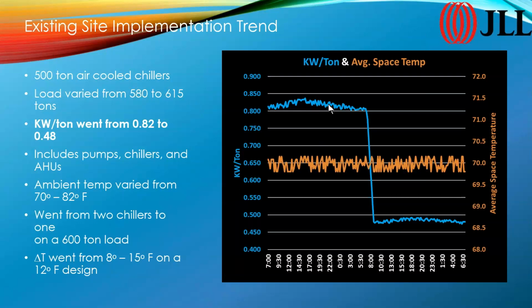We were running with 2 chillers up top, and when we finished the process, we had a 600-ton load, and we were running with 1 chiller quite easily. It was running around 75%, something like that. So a 500-ton chiller with a 600-ton load. That's all right. The delta T went from 8 degrees to 15 degrees. The design was 12 degrees. And just so you know, what we were doing was changing the delta P set point a little bit at a time.